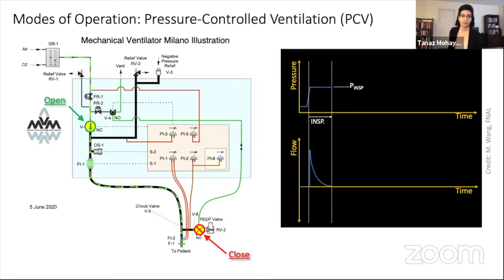During that time, the pressure increases until it reaches the maximum preset value, labeled as P INSP on the pressure versus time waveform at the top. The ventilator then continues to keep the pressure constant over the inspiratory phase, and the inspiratory flow during that time goes down until it reaches zero at the end of the phase.